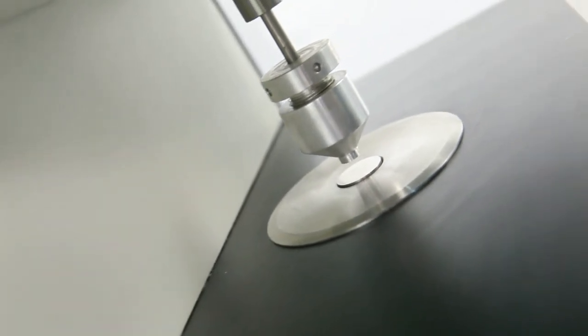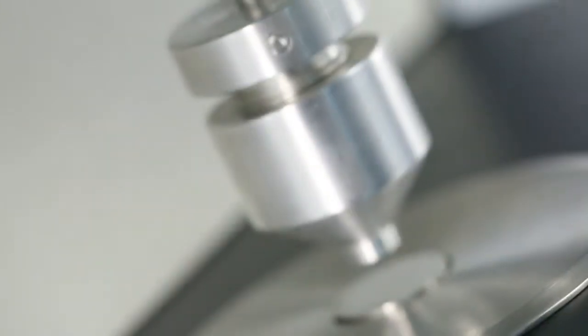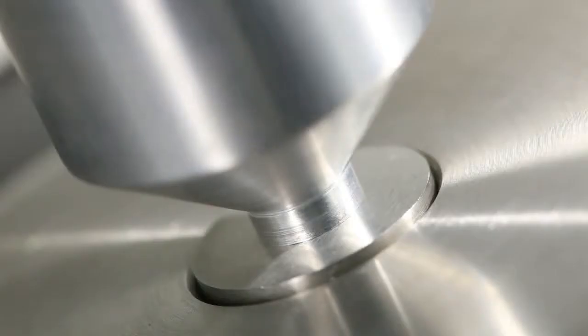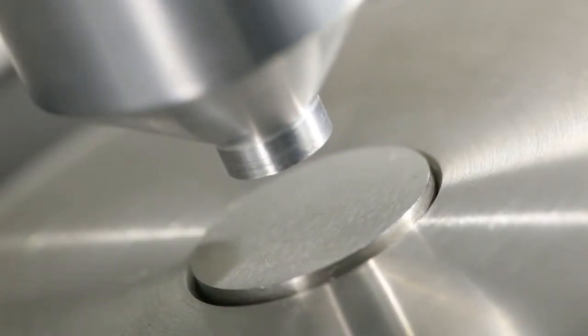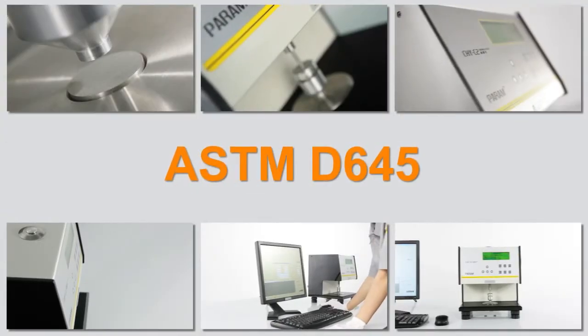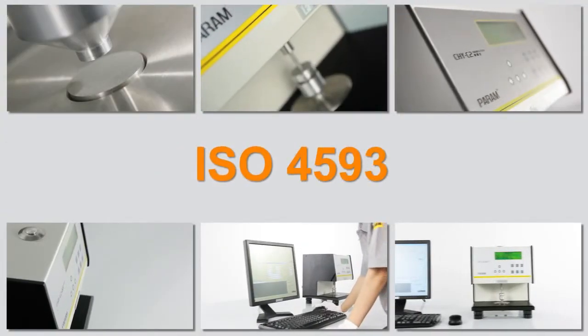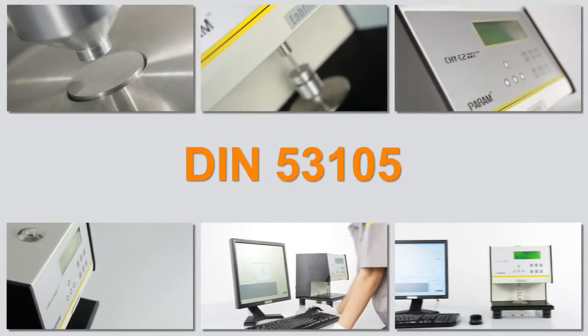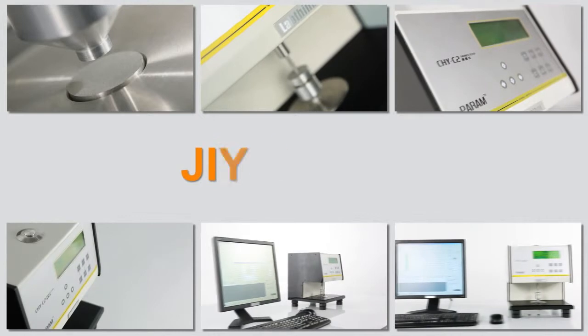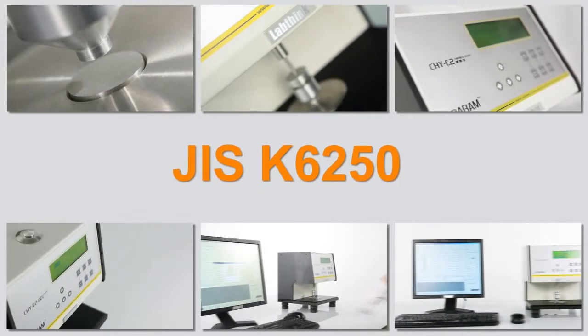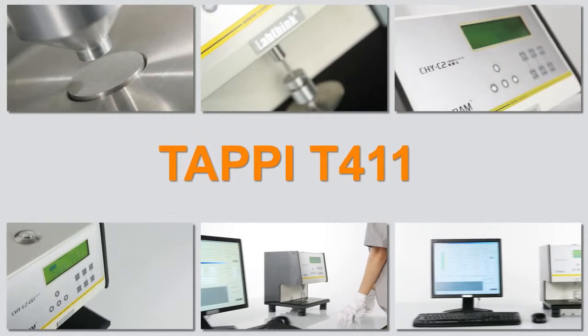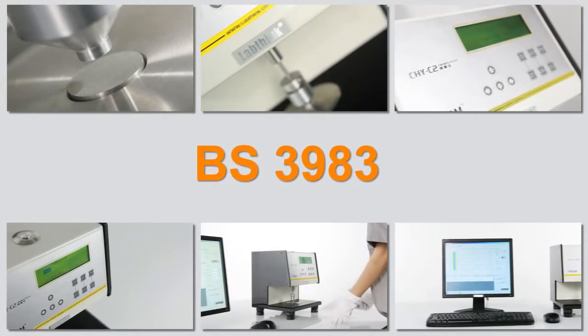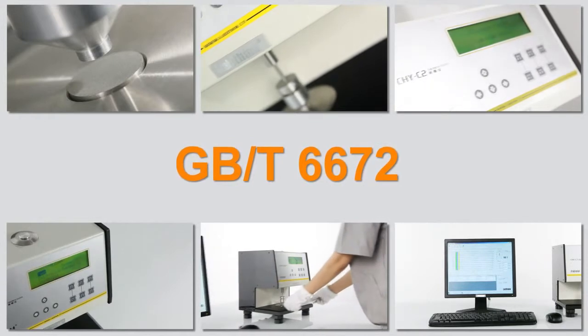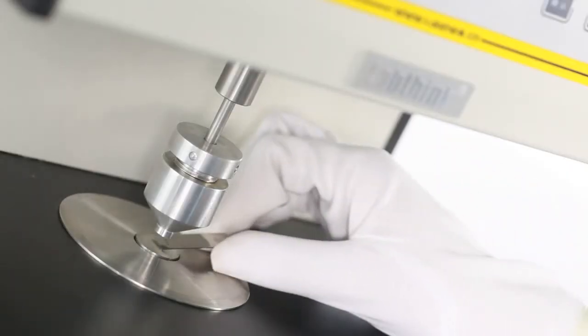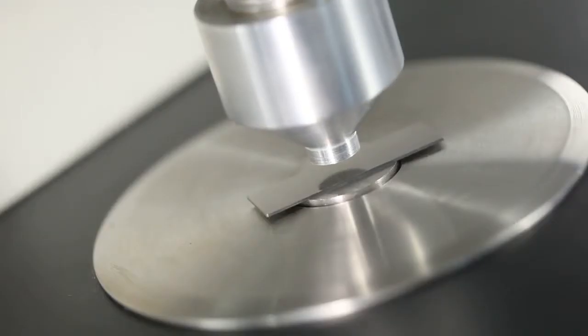The measuring head is designed strictly according to the specific requirements of relevant standards for contact area and test pressure. The testing principle complies with ASTM D645, ISO 4593, DIN 53105, JIS K6250, TAPPI T411, BS 3983, GB/T 6672, and other standards. The instrument can be easily and quickly calibrated using the standard gauge blocks provided.